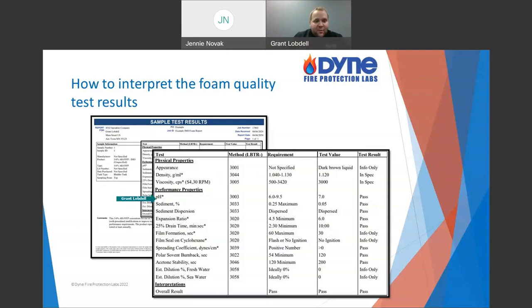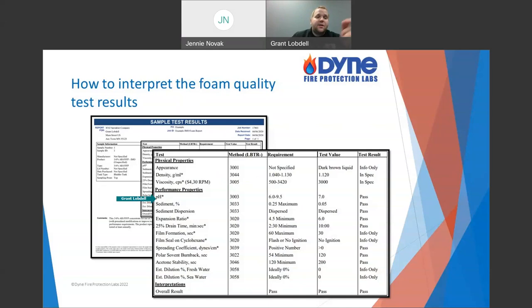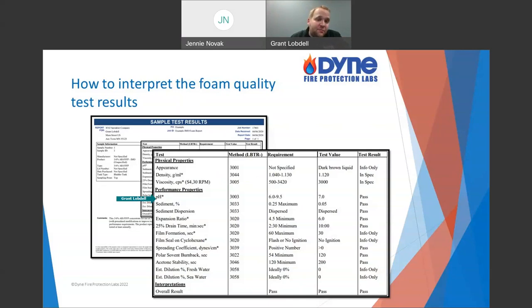The last property to discuss is pH. IMO requires pH to be between 6 and 9.5, and it will fail if outside those values. Most foams are designed to be fairly neutral — 7 being neutral, and the industry standard range is generally 6 to 9.5. Why would it be low? Water dilution can affect it — if rusty water got in, it might be around pH 5. Even neutral water at pH 7 can dilute the buffers — chemicals designed to keep pH stable — making them less effective. Age can certainly shift pH either way.